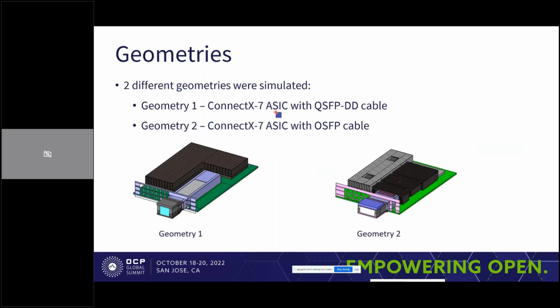I also simulated two different geometries: one is ConnectX-7 with a QSFP DD cable, and one with ConnectX-7 ASIC with an OSFP cable, just to see if we see the same trends for different geometries. These two geometries are not completely different, but here we have a bigger heatsink, and here you have a bigger cable and also a heatsink on top of it. So I would say geometry 2 just has more density than geometry 1.